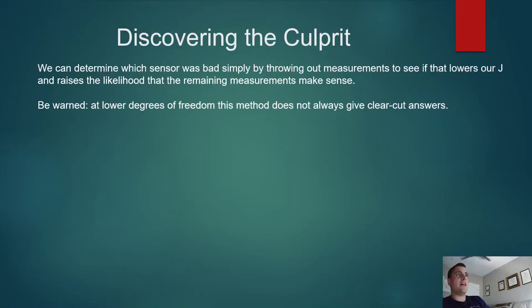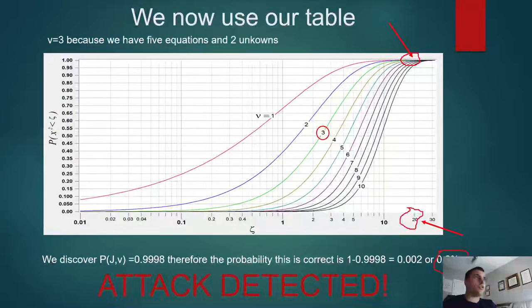Okay, well that's great, but now how do we discover who the culprit is? Well, it's actually pretty simple. We can determine which sensor was bad simply by throwing out measurements and seeing if that lowers our j. If it lowers our j, then it's likely that that measurement was the one that was messing us up. But as you can see by this chart, when you throw out measurements, you lose degrees of freedom. So now instead of operating on the three line, we're operating on the two line. If you don't have lots of redundant measurements, you won't get a clean answer often.